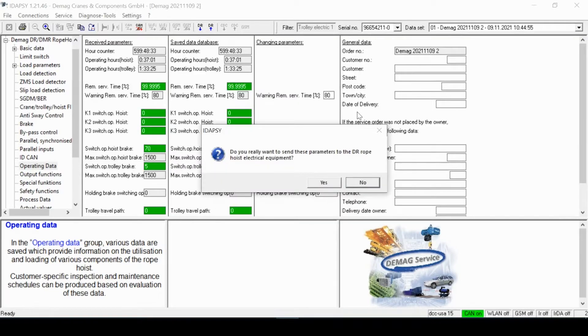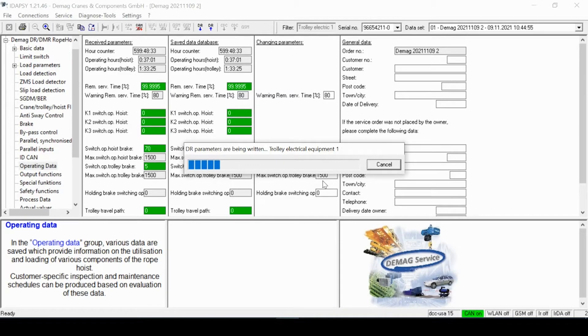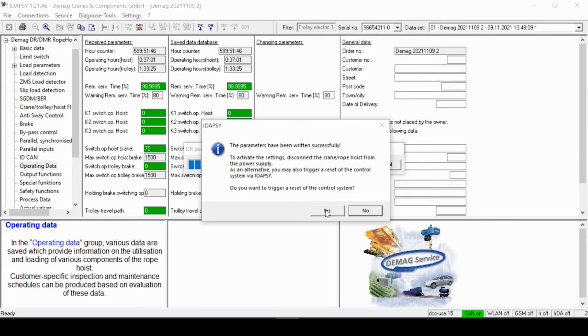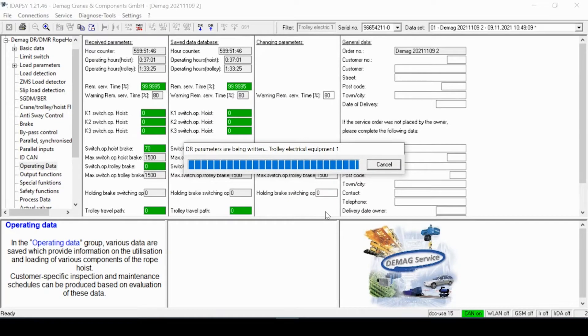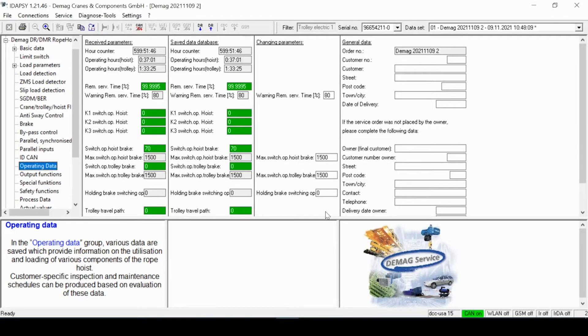The system asks if I really want to send these parameters to the hoist. I say yes. It feeds these values to the board to trigger a reset of the system — it's simply in software — and I say yes, make the changes. I get an audible tone, and notice that my K1, K2, K3 counters have now turned to zeros, as well as my trolley brake switch counter.